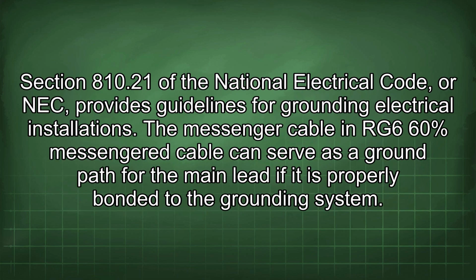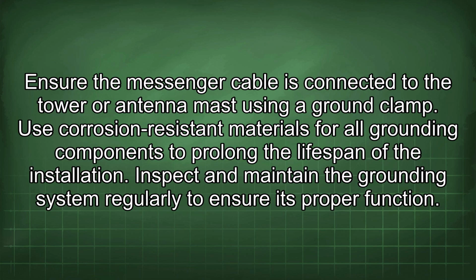Section 810.21 of the National Electrical Code, or NEC, provides guidelines for grounding electrical installations. The messenger cable in RG6 60% messengered cable can serve as a ground path for the main lead if it is properly bonded to the grounding system. Ensure the messenger cable is connected to the tower or antenna mast using a ground clamp.